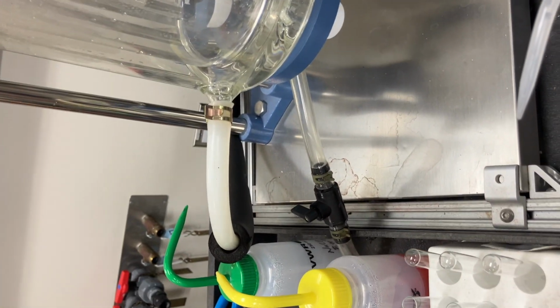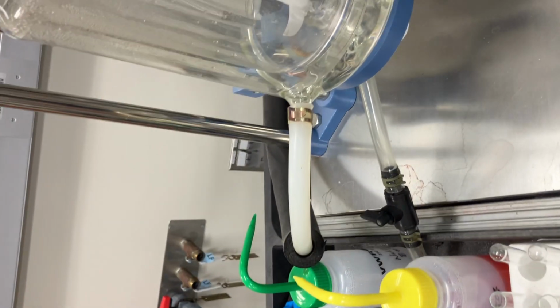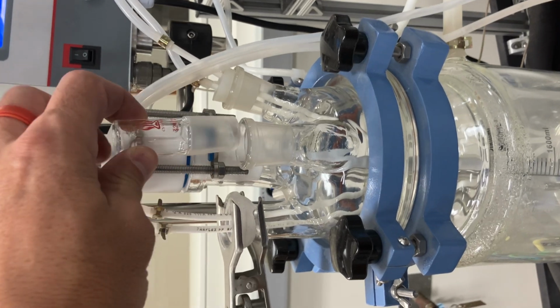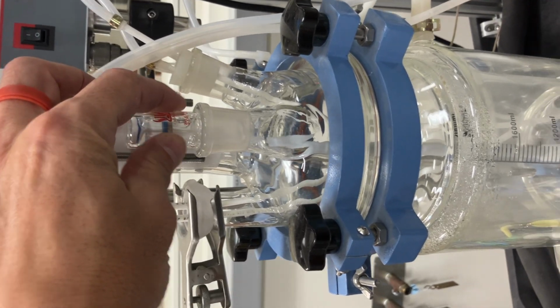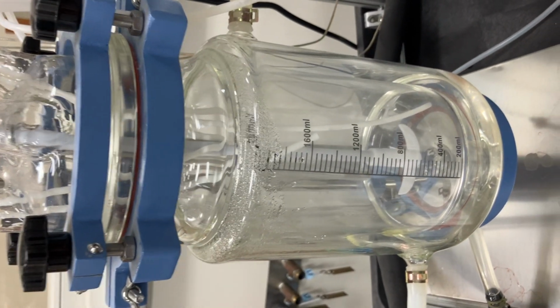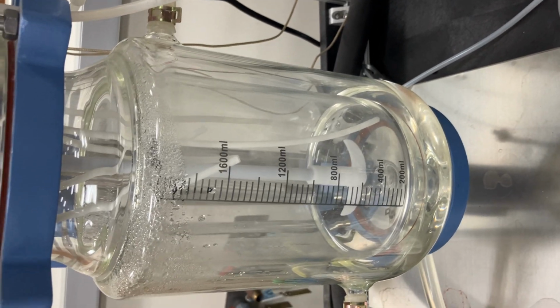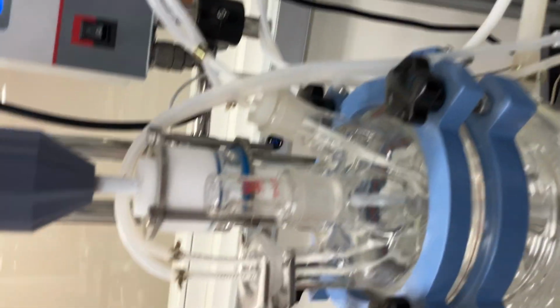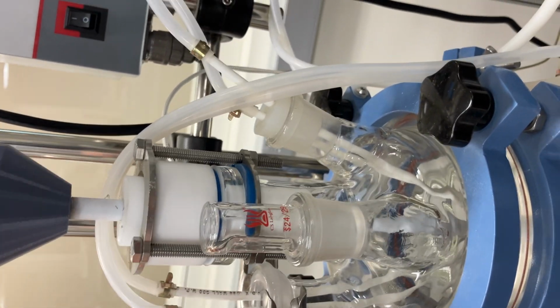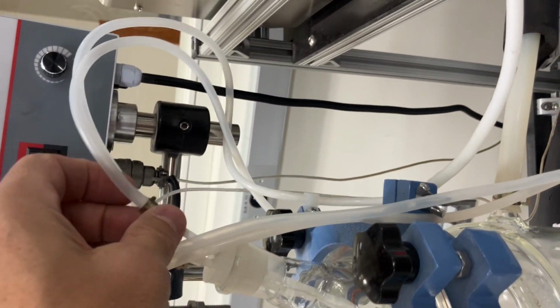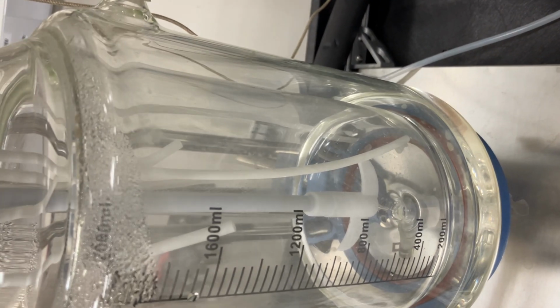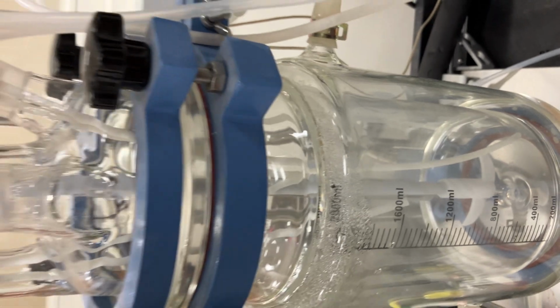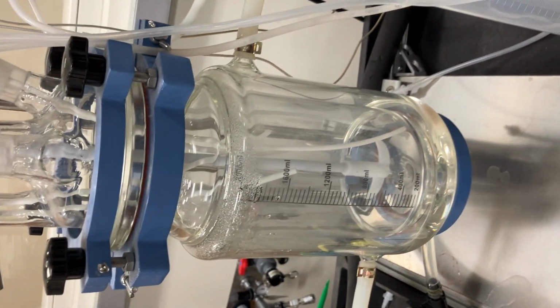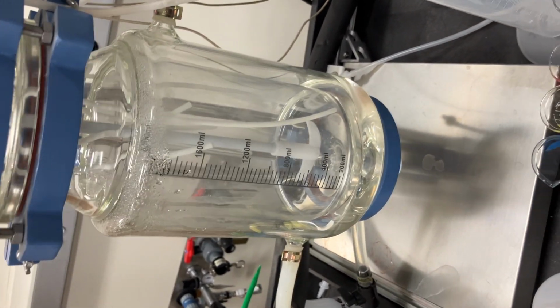There's the drain port. You can open that when you're ready to drain. It'll go out to the drain. When you do drain, it can be vapor locked, so you can open this to make sure there's air in there to allow it to drain. To pump into and out of the reactor, you're going to use these ports here. These go in, and then there's one of them, the longer one, that goes all the way to the bottom. You'll use that one to pull material out. So you can pump in and pump out.